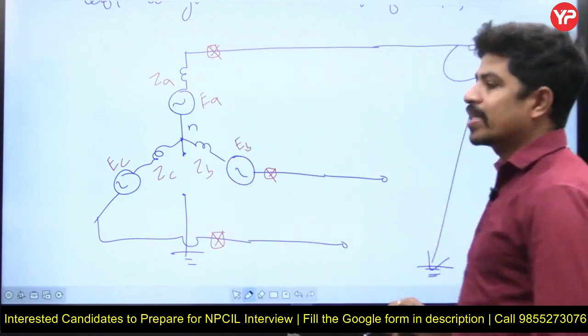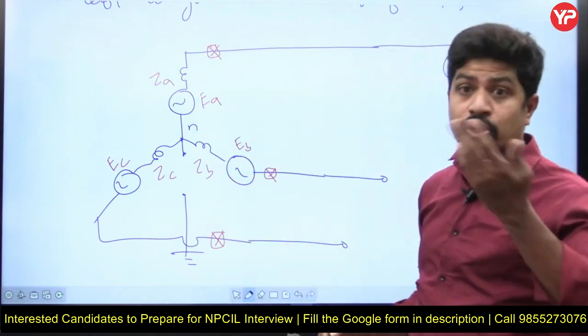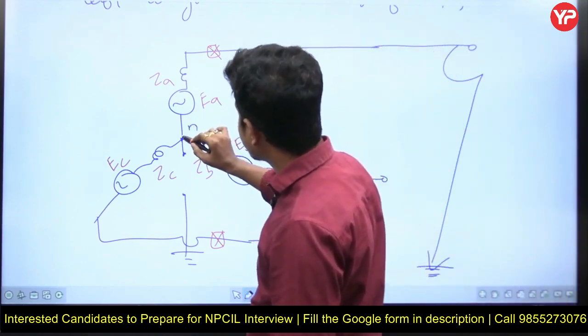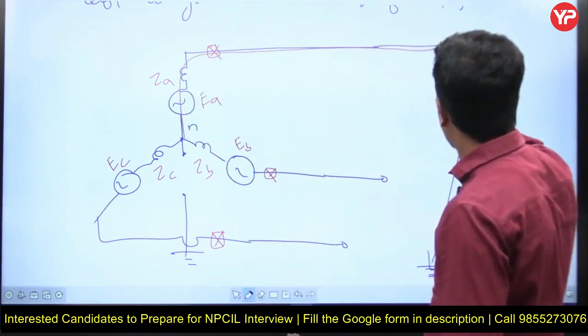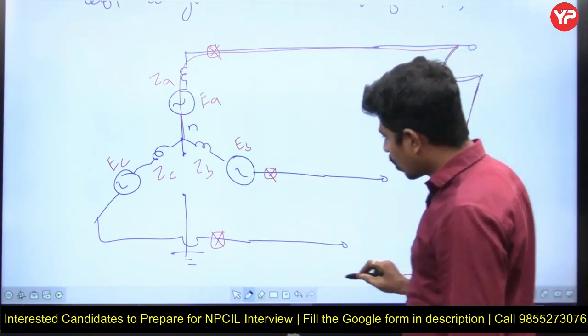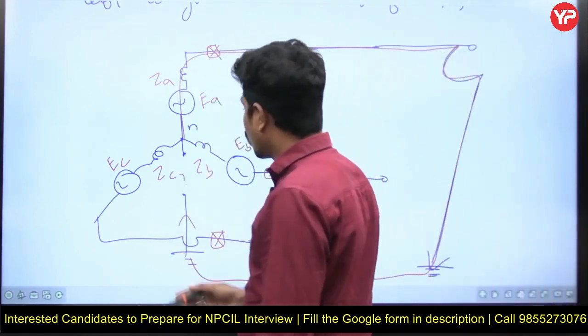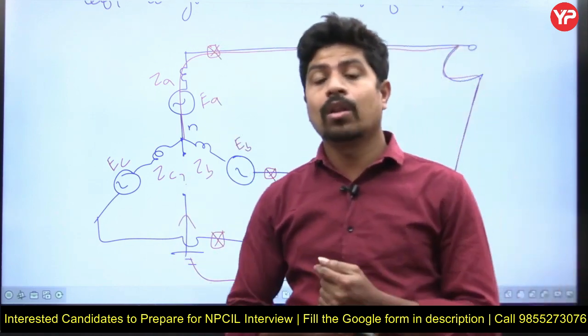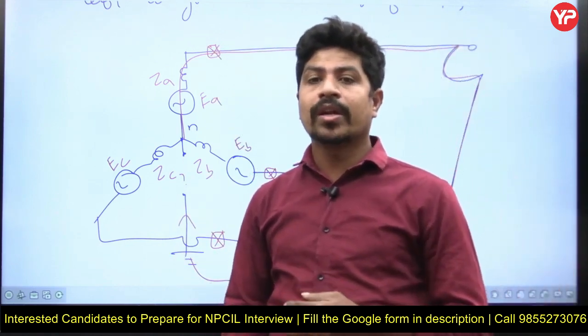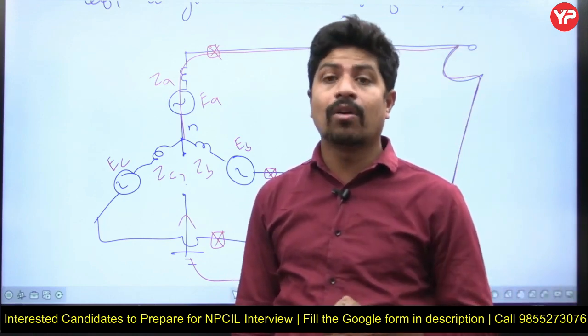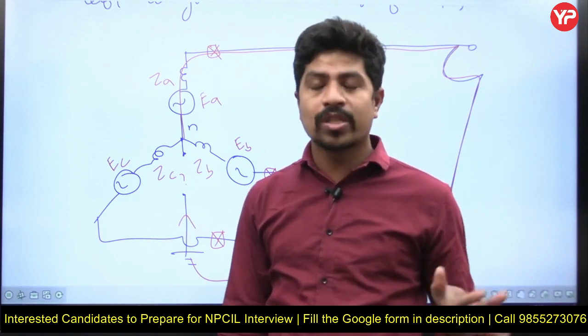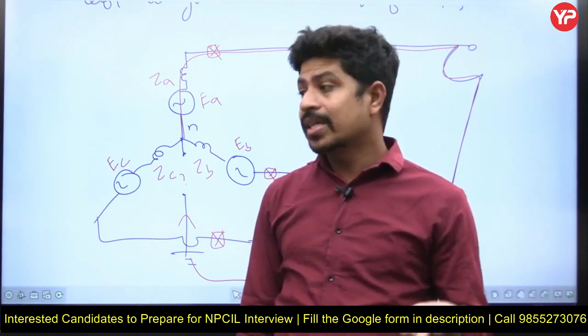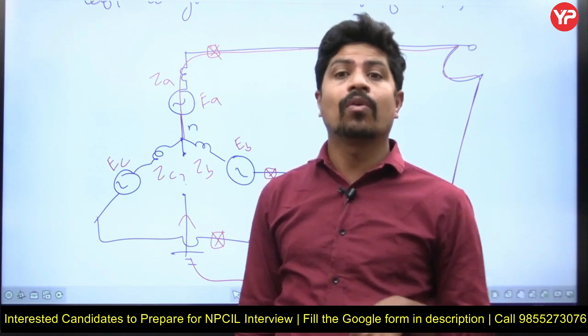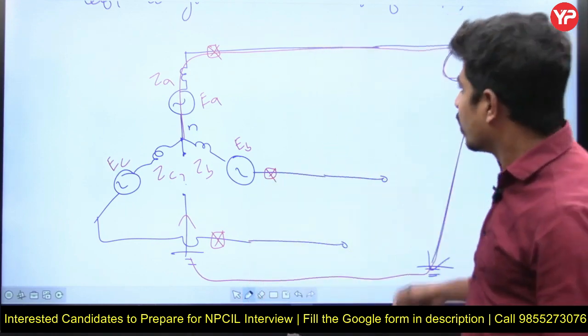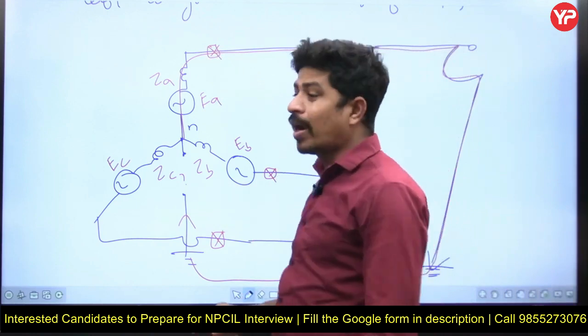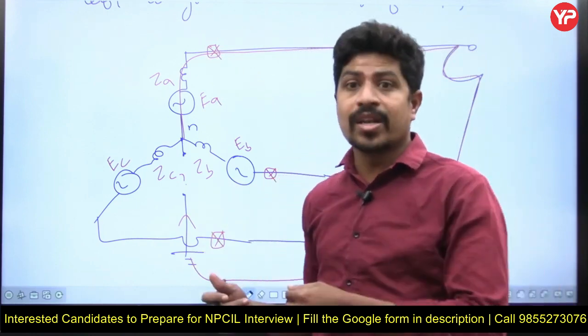Now see, for example, let's assume that fault current is flowing. Fault current is coming from phase A. When it is coming from phase A, it has to end at phase A, from ground. But here there is no closed path, therefore fault current will not flow. If the neutral of the generator is left ungrounded in case of LG fault, fault current will not flow, since there is no closed path. Now people will say, sir, it's a good condition if fault current is not flowing. No, it's not a good condition, because if fault current is not flowing, the circuit breaker and relay are not in a position to recognize the present condition as a fault condition.